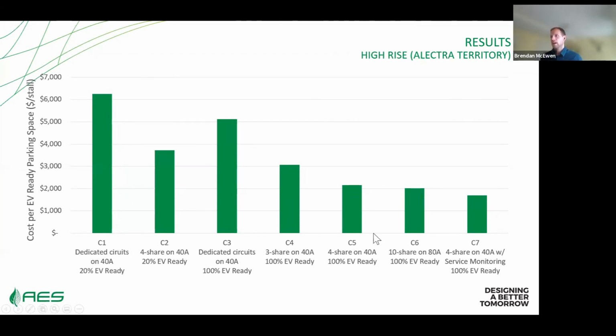And then here we've got the 100% EV-ready scenarios. So what we see is that, as one might expect, if you do this with dedicated 40 amp circuits to each parking space, you're looking at a relatively large amount of copper, significant utility service size upgrades to the buildings, and a much higher cost, in this case about $5,000 per parking space.